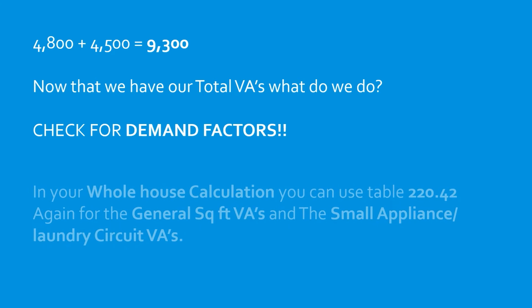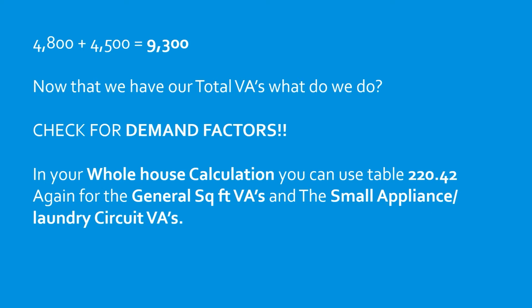Now that we have our total VAs in any question, what do we do? We're going to check for demand factors. Up until this point, I had not shown you how to apply demand factors to any part of the whole house load calculation, so we're going to do that now. In your whole house load calculation, you will use table 220.42 again for your general square foot VAs and the small appliance and laundry circuit. And we're going to practice this a bunch, so don't worry. So we had 9,300 VAs total.